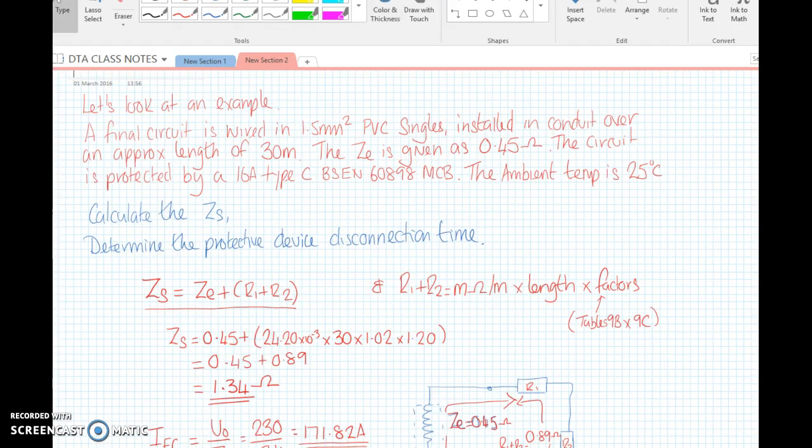During normal operating conditions we can actually lift that value of resistance by using these factors. The most common cable would be 70 degrees C. If it's incorporated in a cable or bunched in a conduit, normally the factor would be 1.2. If it's just singles that are well spaced, we get a lower factor.